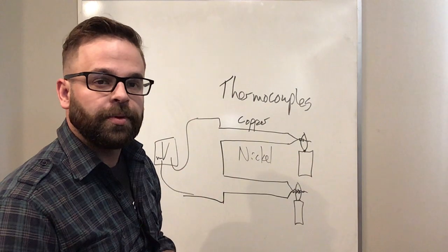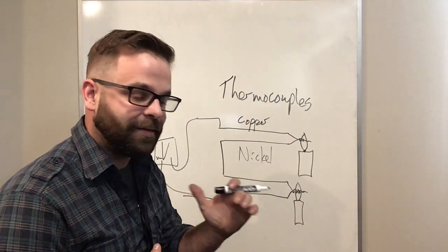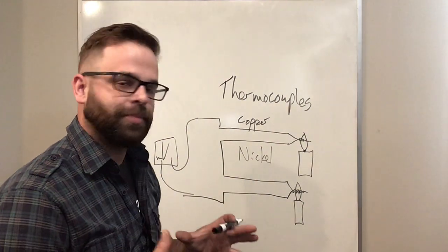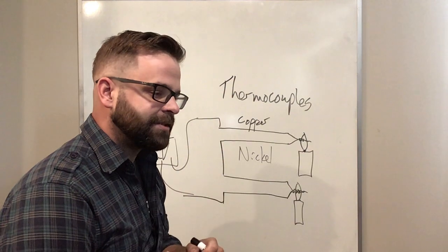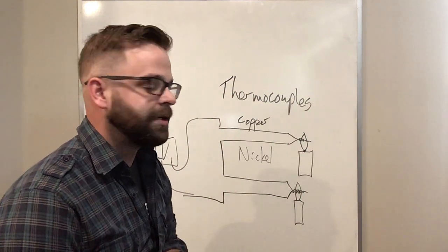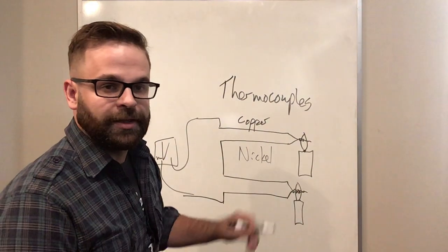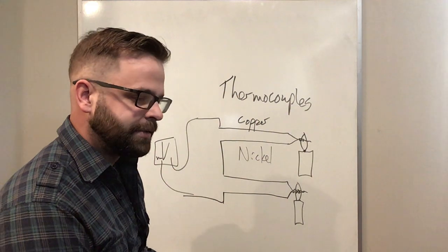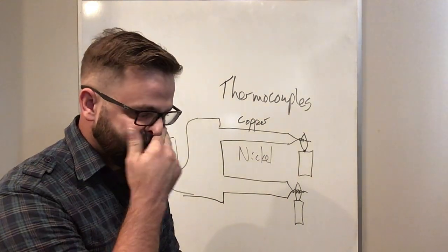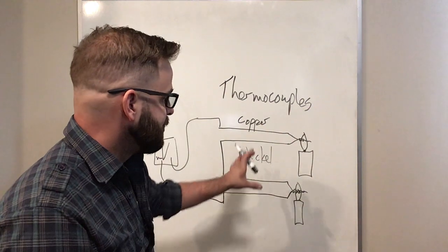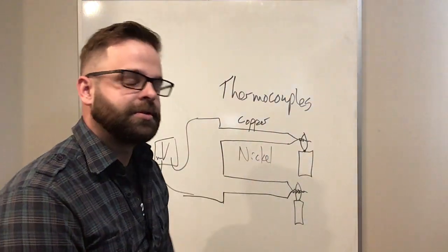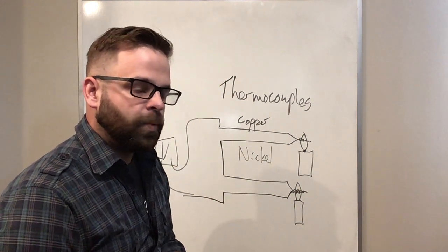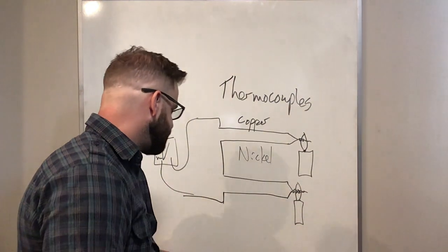The term for multiple thermocouples that are added together, the reason why I say pile, is they're called a thermopile when you have multiple thermocouples added together. So if I wanted a greater voltage output or a greater potential difference from one side to the other, I would end up using a thermopile. And as I've said to some of the classes already, this type of instrument ends up being used primarily in heating situations when I want to control a gas valve.